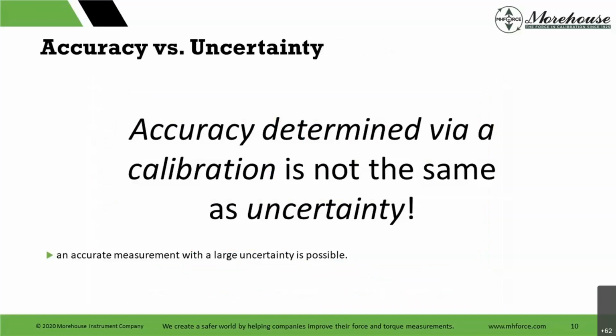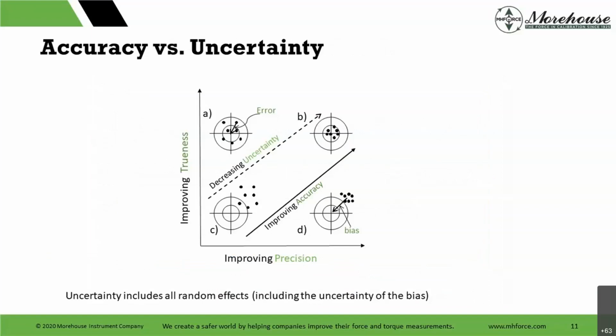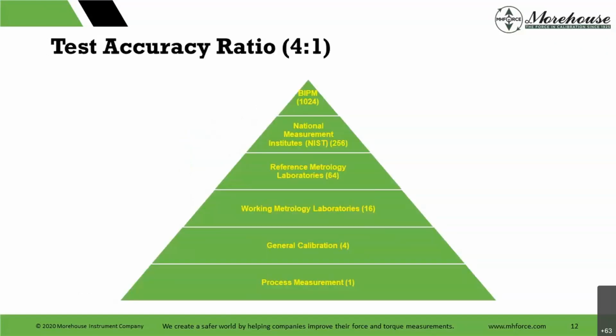So accuracy determined via calibration is not the same as uncertainty. An accurate measurement with large uncertainties is possible. That's the bottom statement here. I thought we had a polling question coming. It's probably coming. So here, again, I like this drawing. This one came out of Eurachem, where it looks like decreasing uncertainty, improving accuracy, and uncertainty includes all random effects. That's really what this is showing.